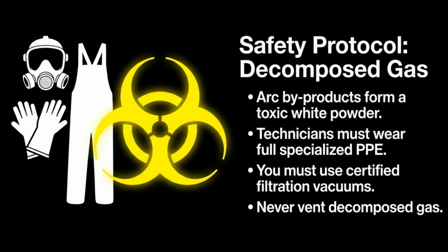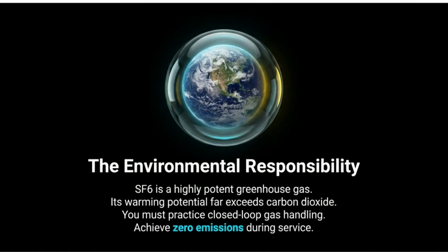Decomposed gas safety protocol is vital. Arc byproducts form a toxic white powder. Technicians must wear full specialized PPE and use certified filtration vacuums. Never vent decomposed gas. SF6 is a potent greenhouse gas, far exceeding carbon dioxide in warming potential. You must practice closed-loop gas handling to achieve zero emissions during service.